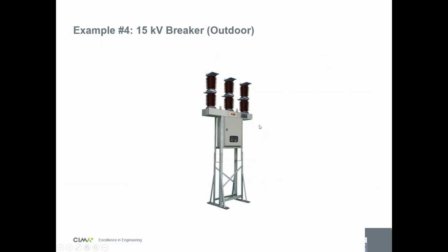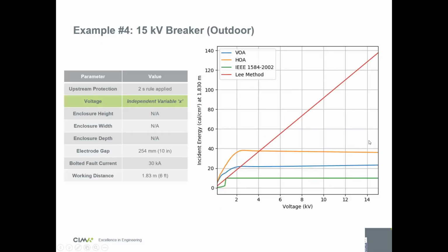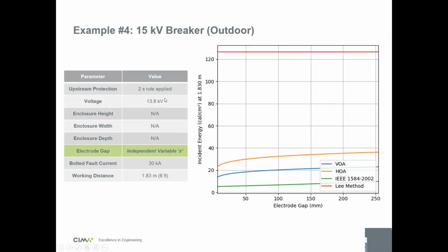So now the last example. It's a 15 kV breaker, which is outdoors. So here I've used VOA, HOA electrodes, and the Lee method. Just to show you how the Lee method is conservative, you see here the Lee method goes way up. And then you have HOA, you have VOA, and then you have the old method. So the old method is lower energy than the new method, but then you have Lee, which goes a step above. So now in this one, the 2-second rule is applied.